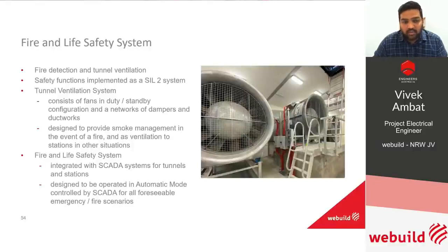There had to be a redesign of the tunnel ventilation exhaust system, which, as shown in the picture of ACS earlier, resulted in two separate ventilation stacks located at the far ends of the station box, along with the implementation of additional wind sensors, because the ventilation system was required to operate in a different mode depending on the direction of the wind, which was identified to be changing during the course of the day.